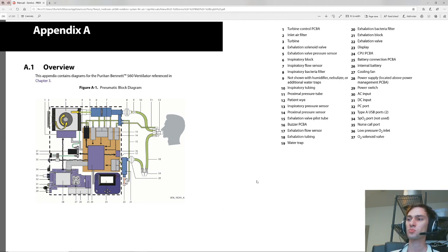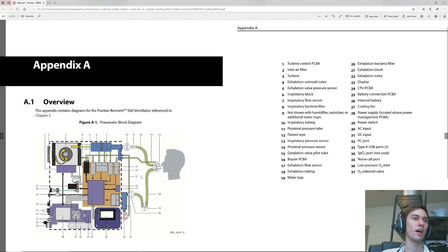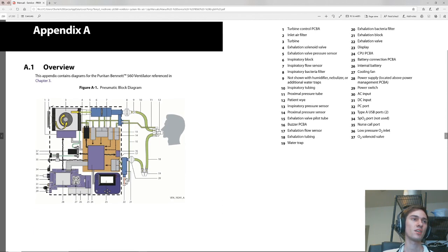Jay Hines, don't hospitals have house pressure lines? Jay Hines, there are a lot of requirements for adjustability on the ventilator side, and this is only a single one of the components in this machine. If you wanted to just use the hospital air, all you do is replace this component, and you'd still have the oxygen solenoid and all this pressure sensing equipment. So I think there's not too much to be gained by replacing that unit. Also, that assumes your patient is in a hospital, and especially as the situation devolves, the possibility of a patient being in a field hospital goes up, which may not have the same infrastructure as a real hospital.